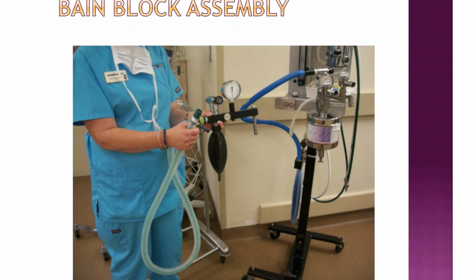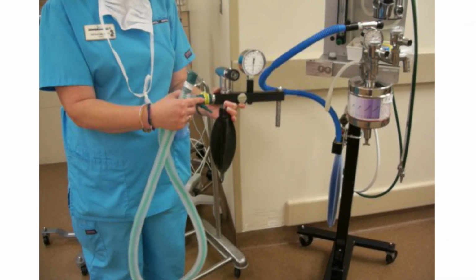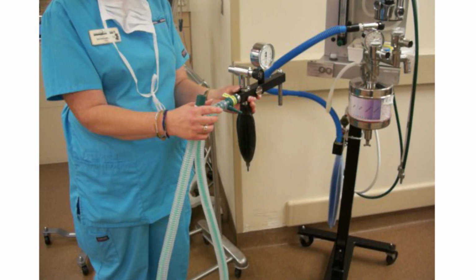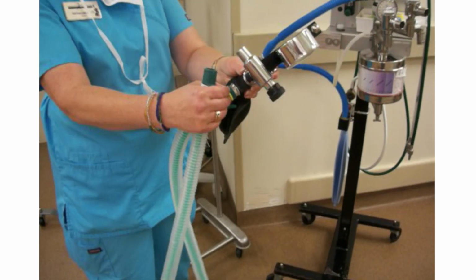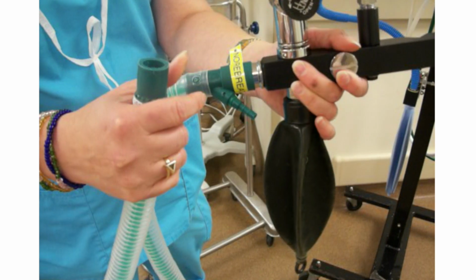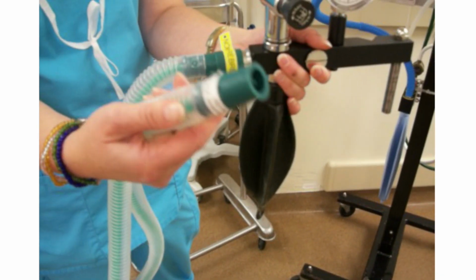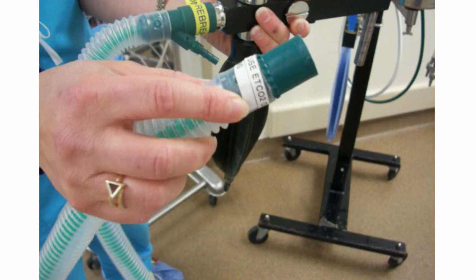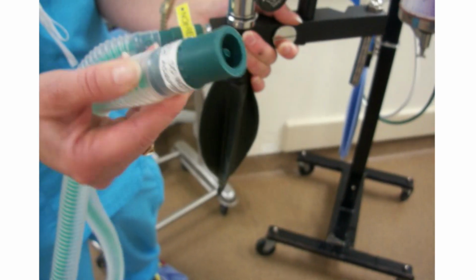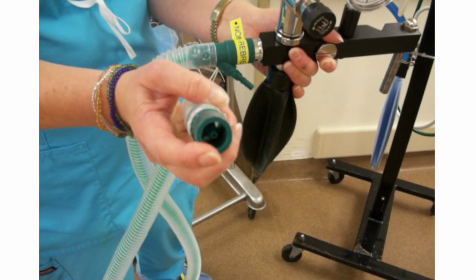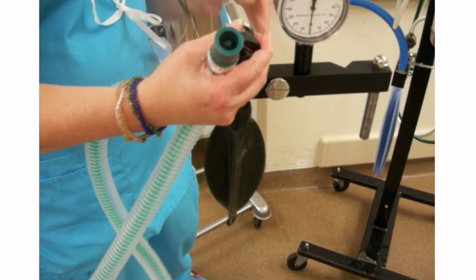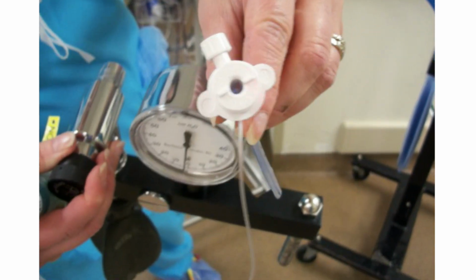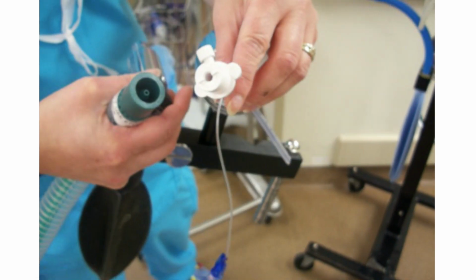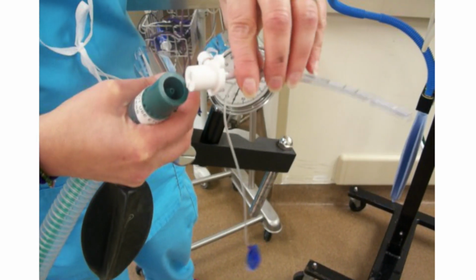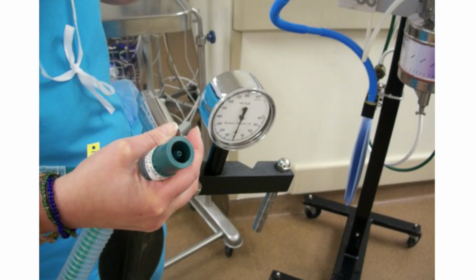Here's a little video on how to hook that up. Okay, I am going to quickly demonstrate how to hook up the non-rebreathing Bain block. These are for animals that weigh less than 7 kilograms or approximately 15 pounds. This hosing is specifically labeled non-rebreathing circuit, so it is dedicated to this Bain block system only. It also clearly says on the edge of the tube here that you cannot use the carbon dioxide dead space adapters on this unit, because the gas comes out of the hole in the very center. When you examine the endotracheal tubes that have the dead space adapters on them, you can see there would only be room for the animal to inhale, and no room allotted for the patient to exhale. So you would not use these on the Bain block.